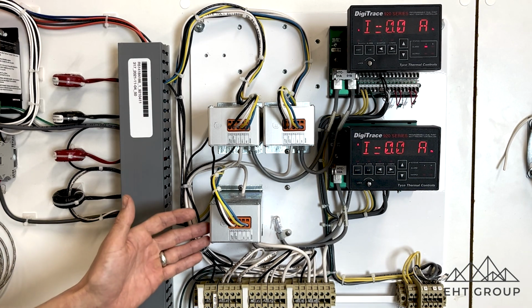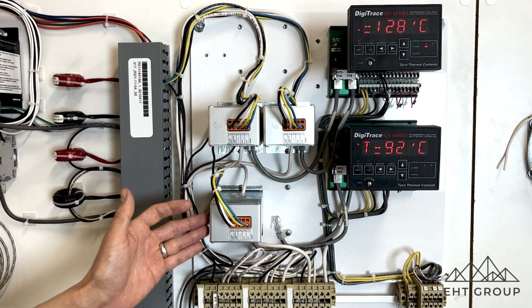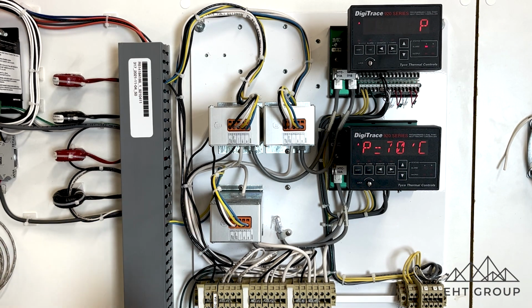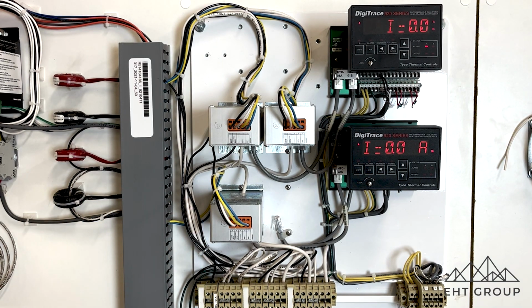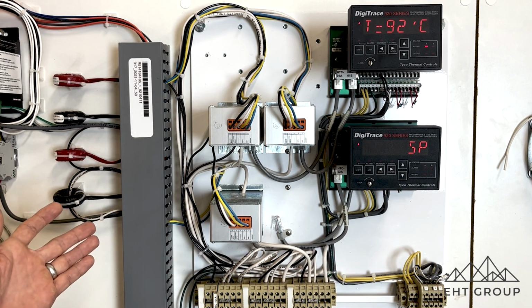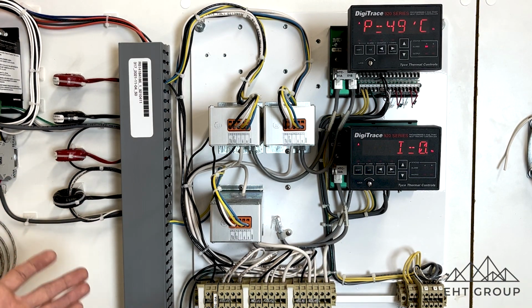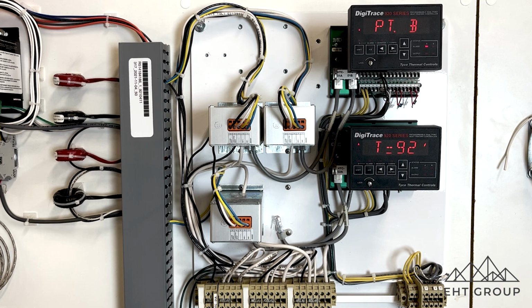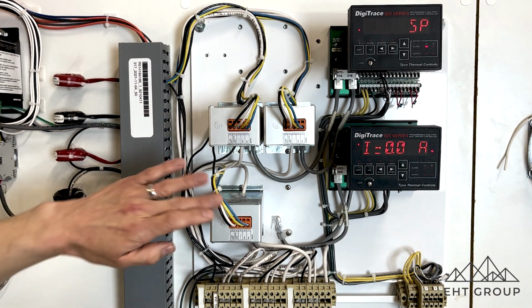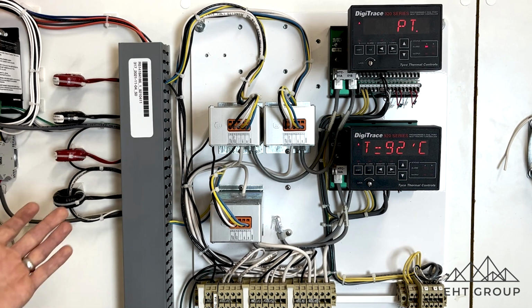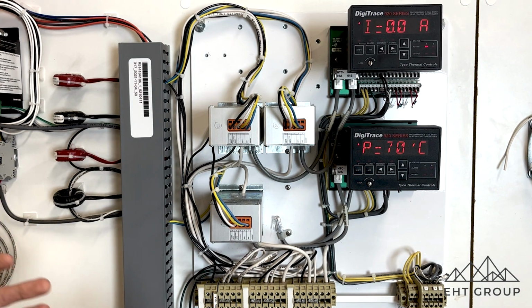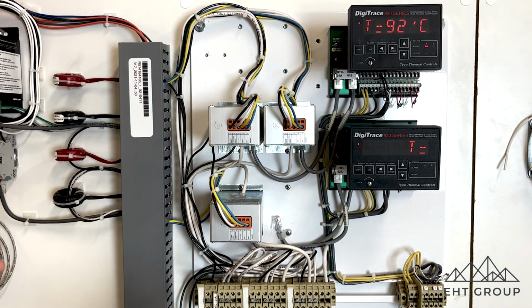So the CT modules will be very specific to either an SSR or an EMR. This one, which is most common, is configured for solid state relays, or SSRs. What is happening here is we have our black and white wire, obviously our supply voltage. And the supply voltage for any of these CTs ranges from 100 to 277 volts.